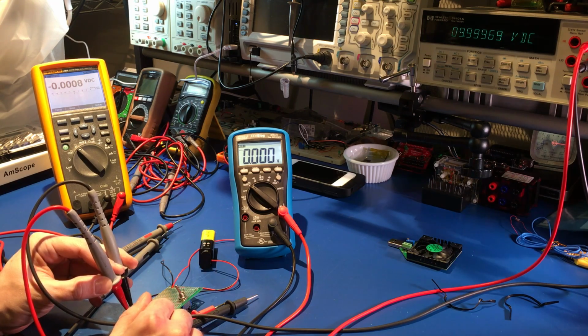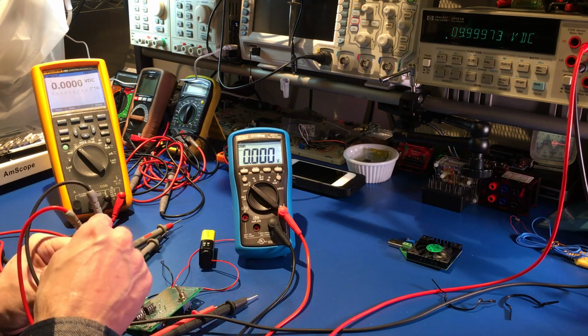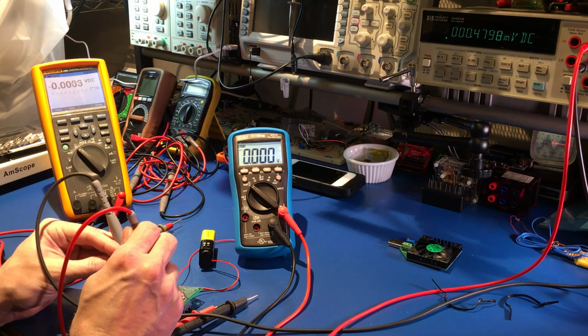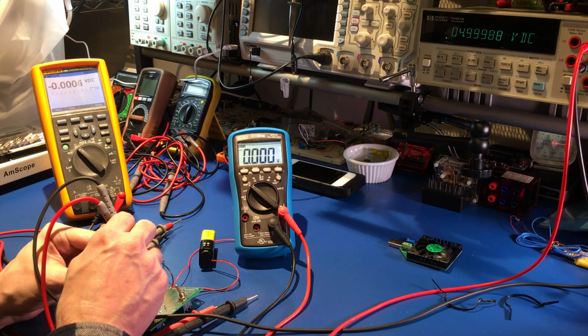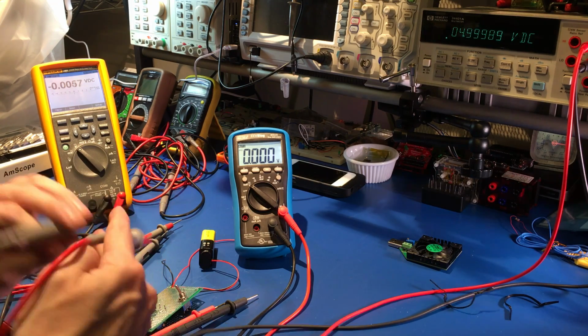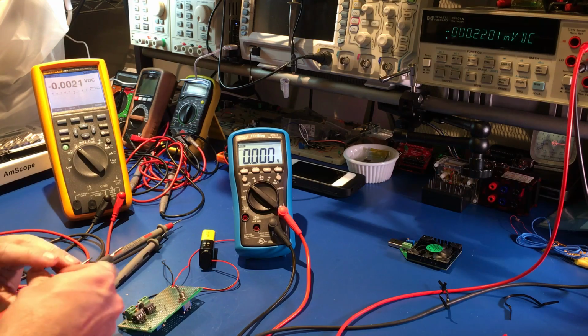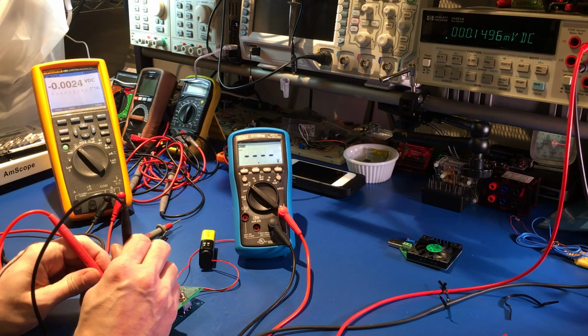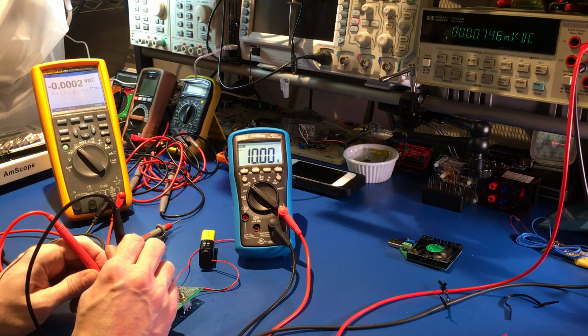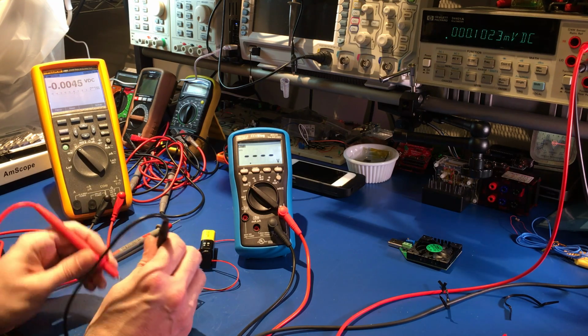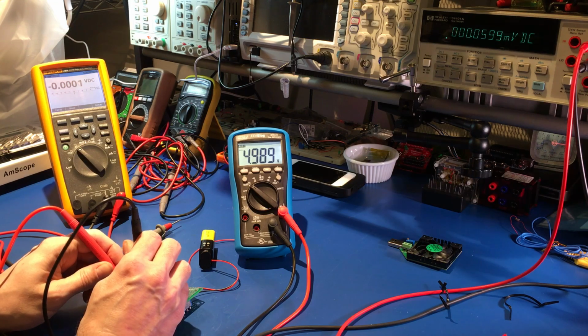Nope, there it is. I'm going to have to give this some time to warm up. It's reading 9.9997172. It will eventually warm up, but right now we know we definitely have a 9.99 without a doubt. And this should be a 5-volt range over here, 4.999. So while we give this some time to warm up, we can still check it based on those numbers. And of course 9.999 would round up to 10. Boom. Dead on. And this one should round up to 5.